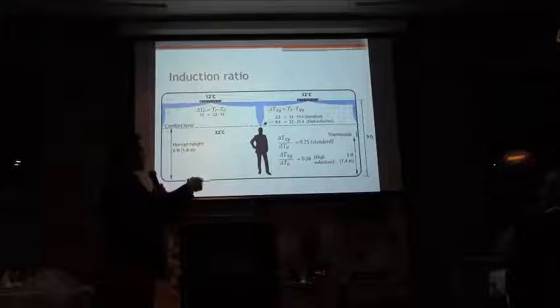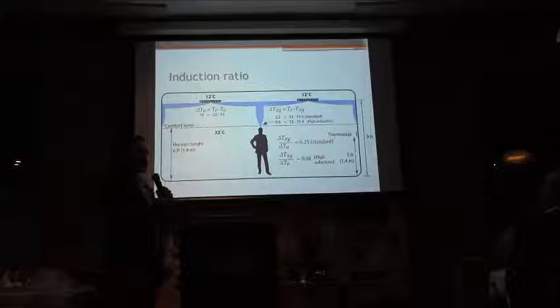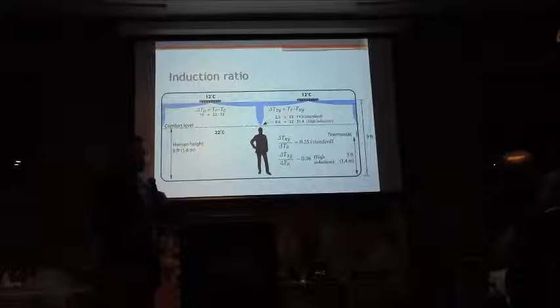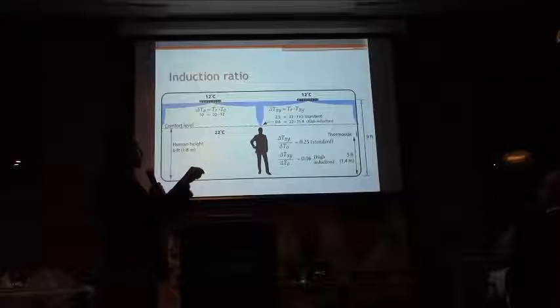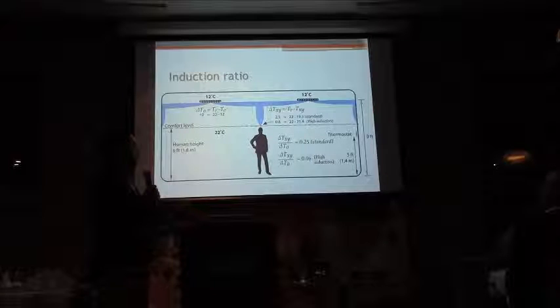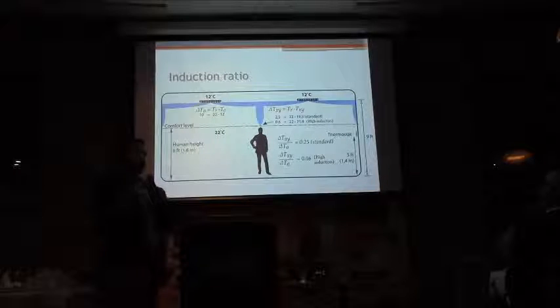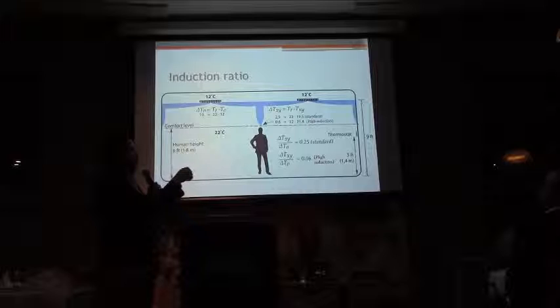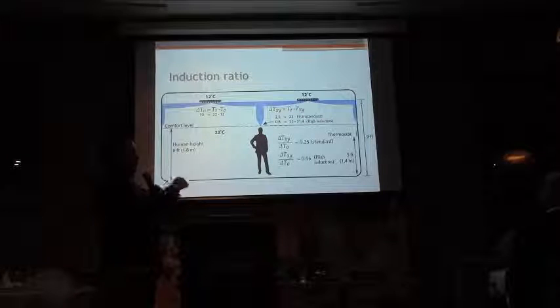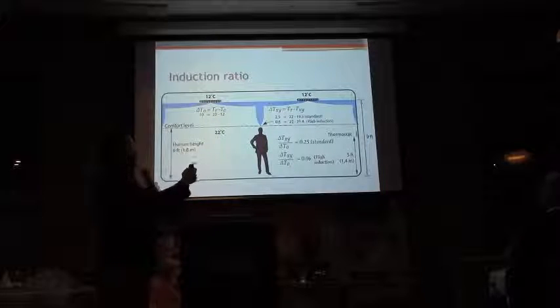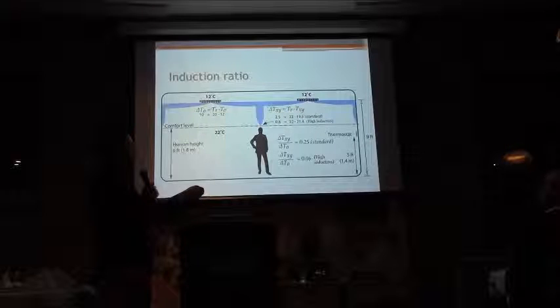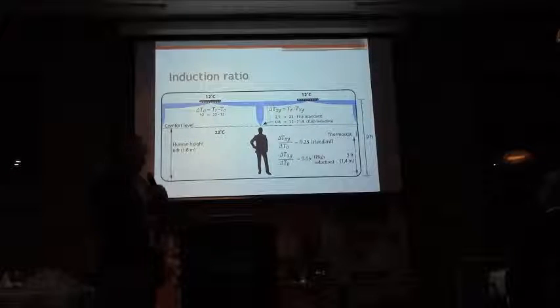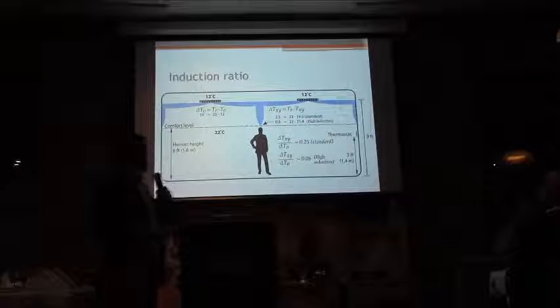And if you notice, anything that's a standard diffuser, whenever I say standard, I actually mean the cone diffuser, because it's the most common diffuser out there. So it's 0.25 in induction ratio. If you do 1 divided by that, it's actually a temperature ratio. So if you do 1 divided by your temperature ratio, you get your induction ratio of 4 for a standard diffuser, and 1 divided by 0.06 will give you 17 for high induction diffusers.